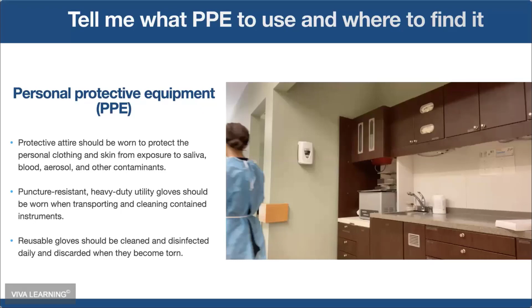So I mentioned earlier, we want to train specific to your Steri-Center. Even though we all might have a very similar flow, it might just look different. But our instrument reprocessing should, no matter what, happen in 5 steps. So we are going to receive our instruments. We should have an area to receive those and decontaminate them. And then they go into a cleaning, rinsing, and drying phase. Then we're going to inspect and package, and that includes our chemical indicators. Then we sterilize, and then we store.